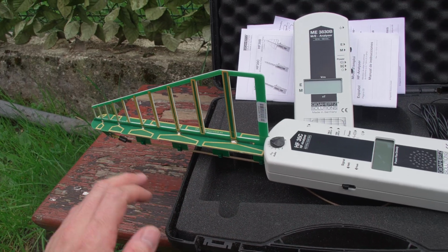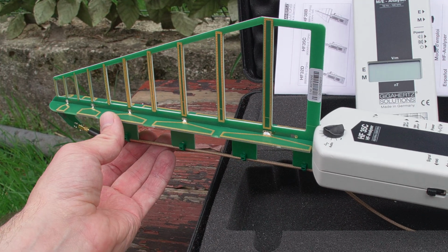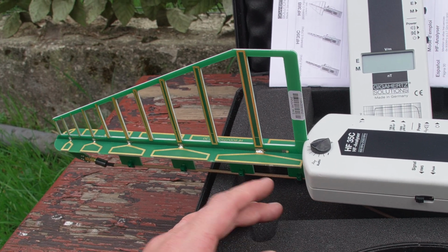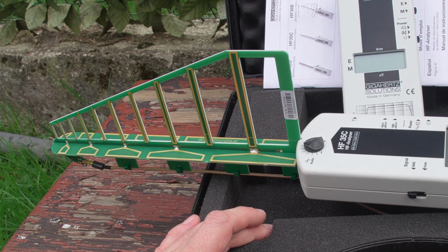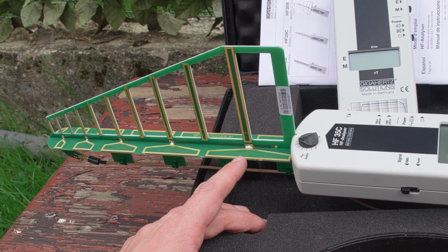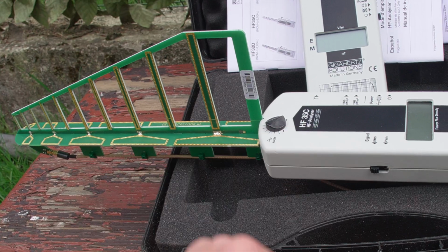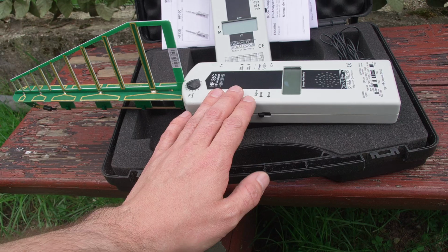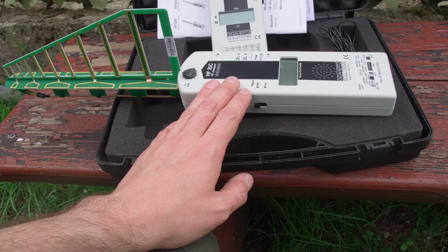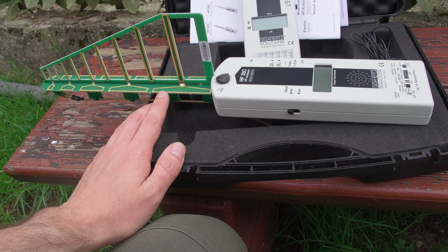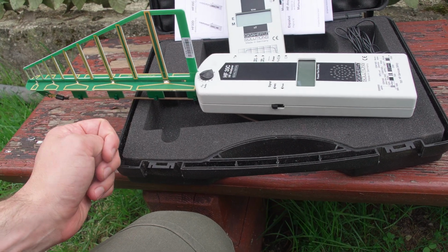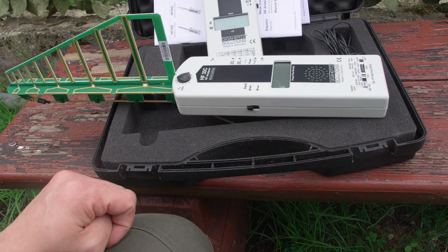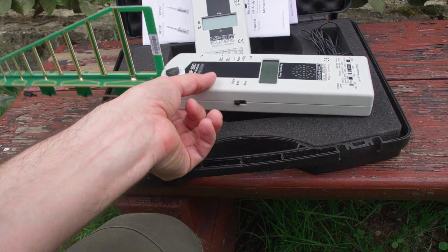The most expensive part of that system is the log periodic antenna that gives you a very good directional ability to measure the source of the interference. I'm also assuming that it is calibrated to that specific instrument, and most likely it holds software calibration data, because it is a very complex and very expensive to make antenna that is responding in a flat curve over a very wide range.